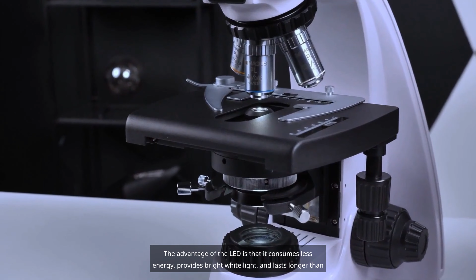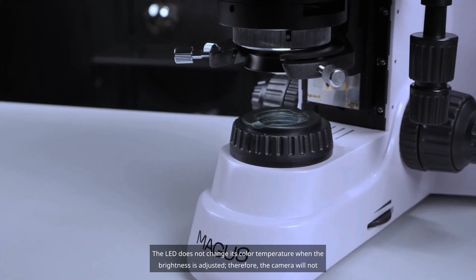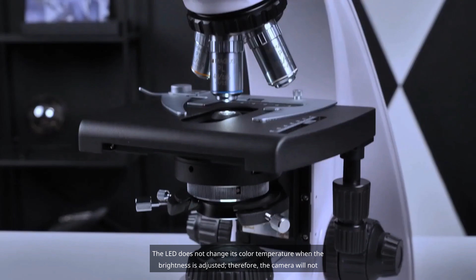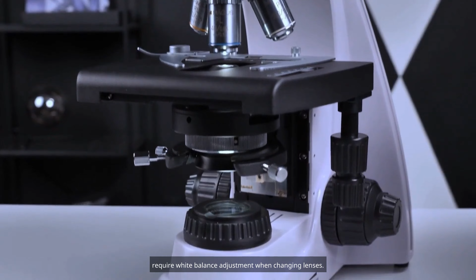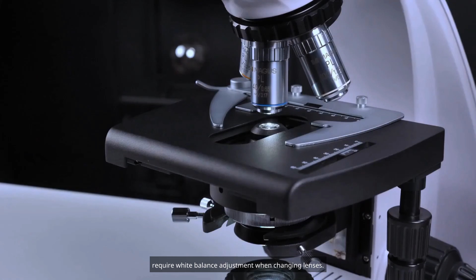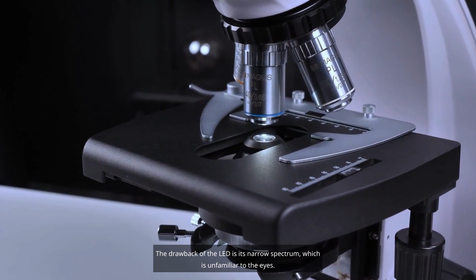The advantage of the LED is that it consumes less energy, provides bright white light, and lasts longer than a halogen lamp. The LED does not change its color temperature when the brightness is adjusted. Therefore, the camera will not require white balance adjustment when changing lenses. The drawback of the LED is its narrow spectrum, which is unfamiliar to the eyes. Therefore, if the microscope is needed for short periods during the day, or if shooting with different objectives is anticipated, choose the LED.